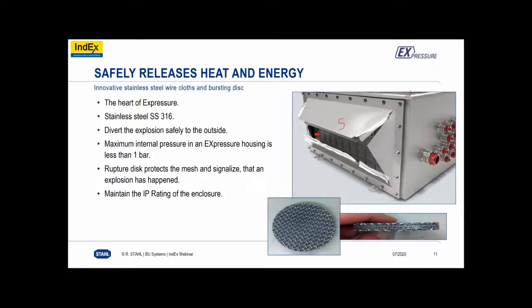Dust layers have to be prevented on the internal and the external surface of the mesh. Somebody just asked, what was the difference between EXD and EXS enclosure? Now, in this enclosure, there is no EXS enclosure here. The overall protection technique, the flame path up here, and where the cable glands are down here, this is the EXD. It's a typical EXD box, but on the left and right hand side is where the pressure relief are.